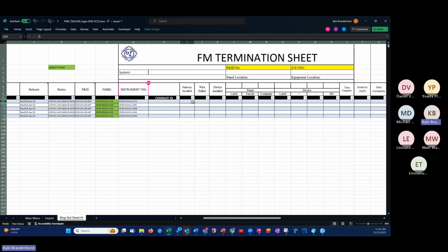who's helping design the model, so we can start naming these conduits, and then you can say if those conduits are installed or not. There's probably going to be, I think, several hundred conduits installed from tray down to different areas. And it's going to be really important that we know which one we're all talking about. It can't just be that conduit over by C7 feeding that thing I can't remember. It's going to be very good for us if we number the conduits, and then we can reference the conduits by those numbers and follow those down, and see all the devices that are in that conduit.